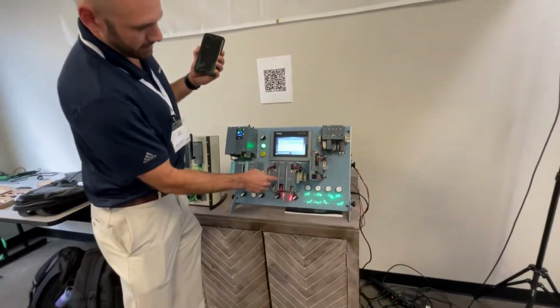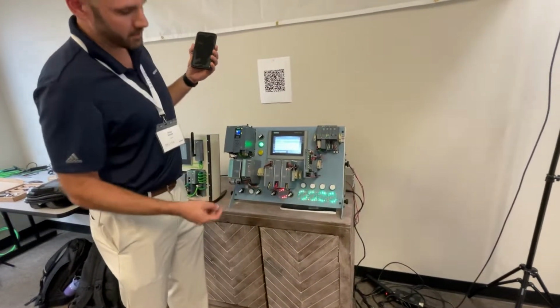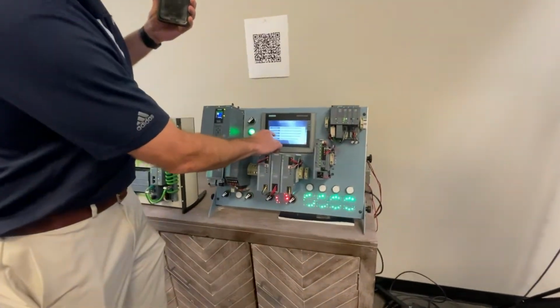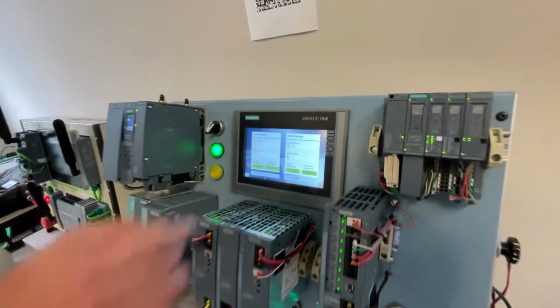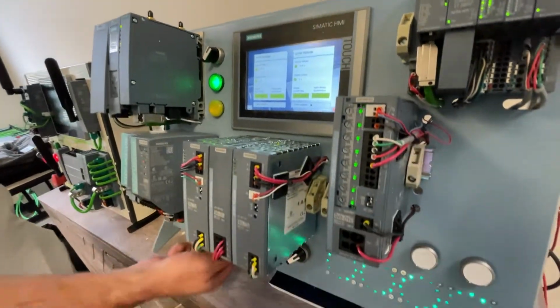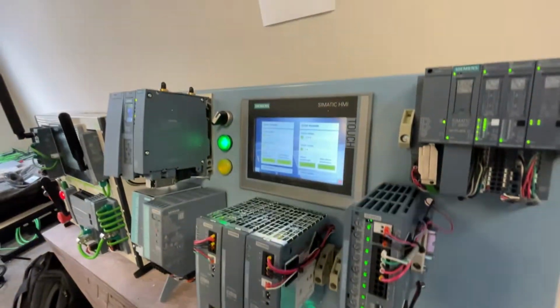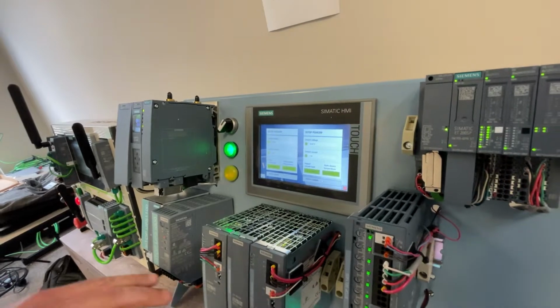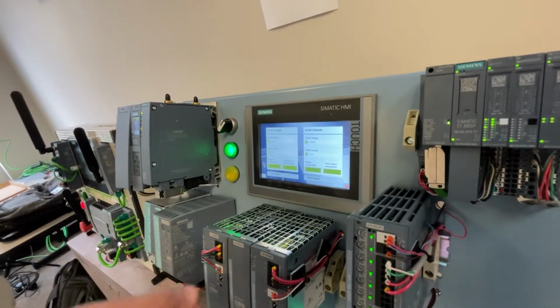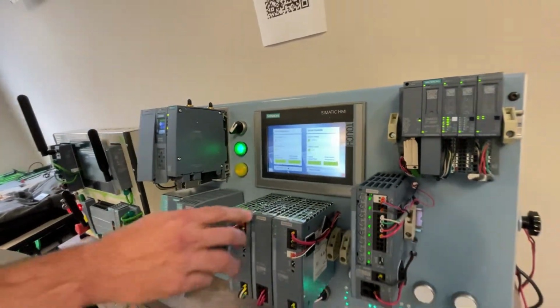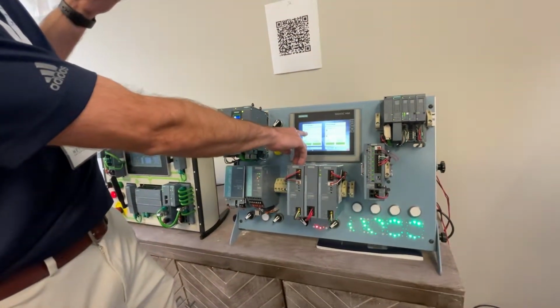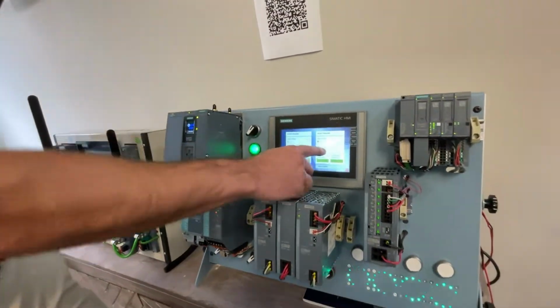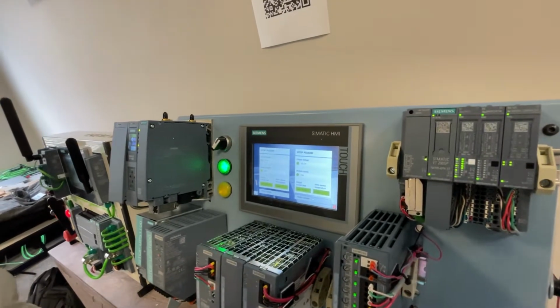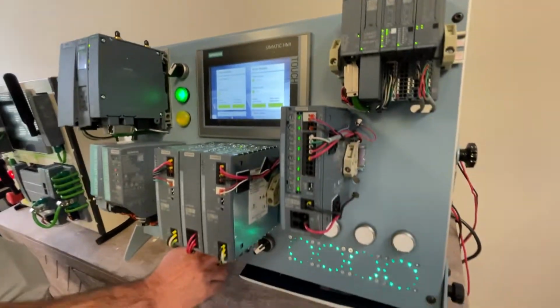Also, you'll see that in between these two power supplies is what we call a redundancy module. So I can go back and show you real quick on this screen here. Basically, this is to provide redundancy of the two inputs. So basically, you have your 24 volts stable. In case one of the power supplies fail, the redundancy module will kick in and seamlessly take over. So you'll notice now that power supply 1 has gone down, power supply 2 is still on, and we're still operating all the LEDs right below the redundancy module.